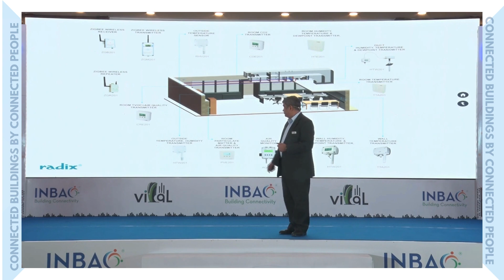Similar with air handling units. We can give you an AHU controller. So we don't make DDCs, I want to be clear. What we do make are good quality PID controllers. And that controller over there has some set configured parameters and control strategies for standard applications. So if it fits, it's a more cost-effective solution for smaller buildings. It also has Modbus RTU, so you can daisy chain these back into your primary controller.